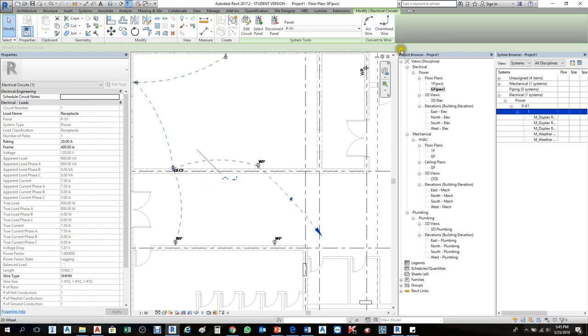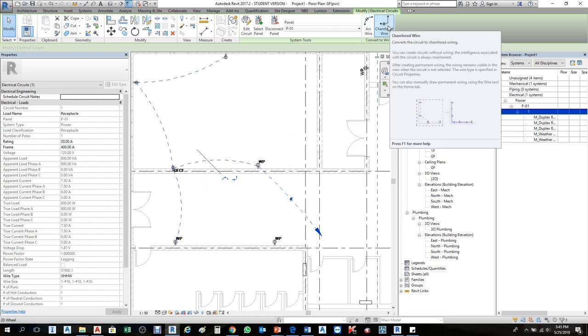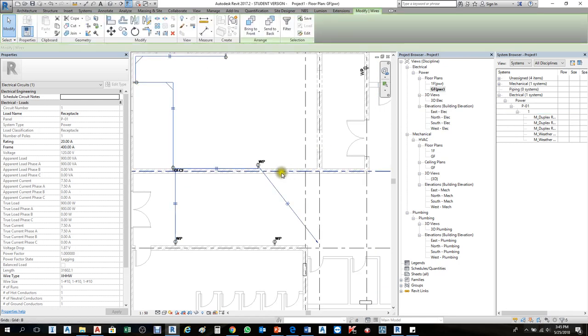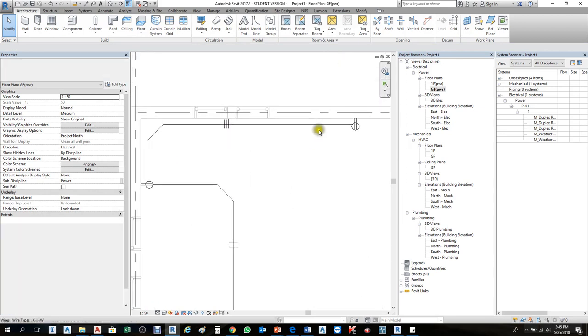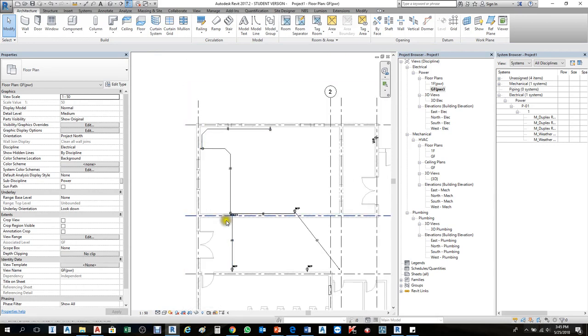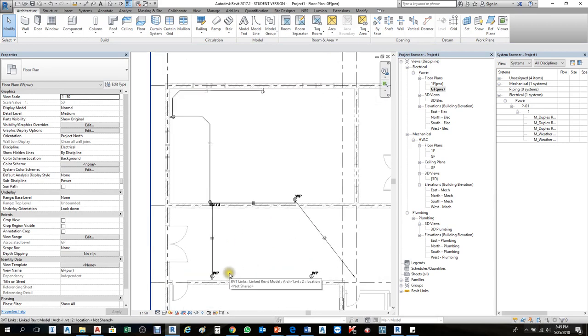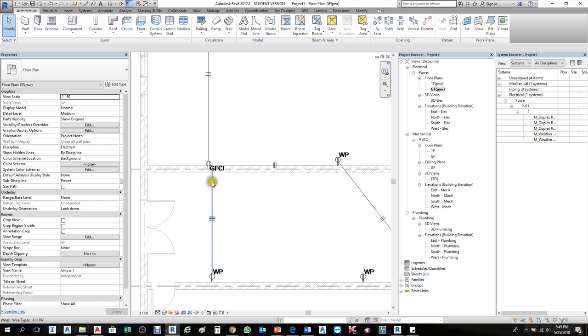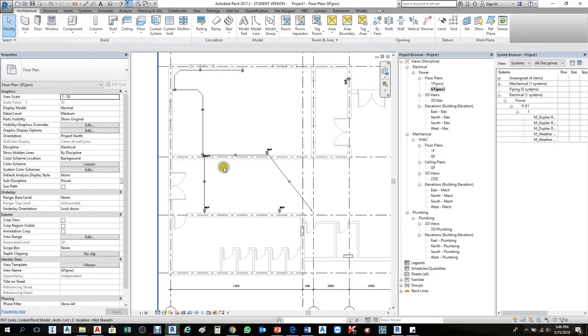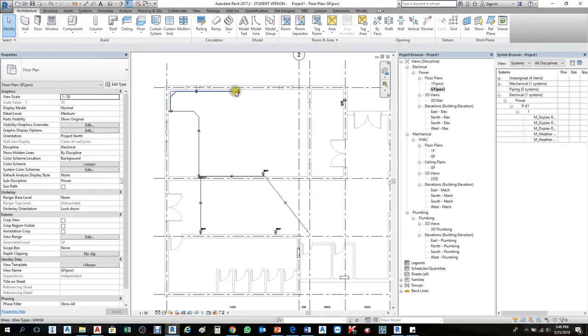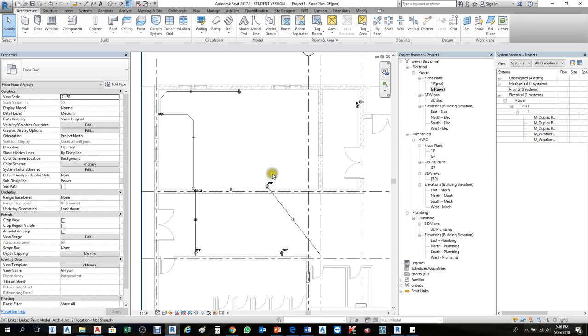After selecting the circuit, choose the wire type: arc wire or chamfer wire. I'll choose Chamfer Wire — this is an indication only. The chamfer wire connects the duplex outlets showing all four connected together. If you don't like part of the connection, select the wire and delete the unwanted segment. To manually reroute a wire to go from the outlet to the panel, use System > Wires > Chamfer Wire, then click the pink circle connection point and draw it.